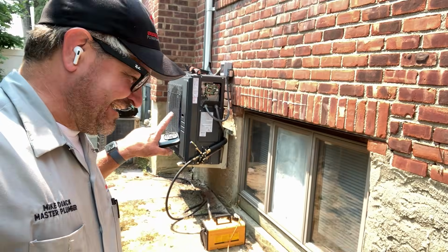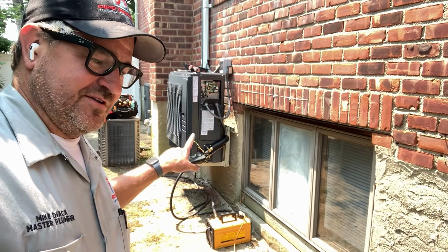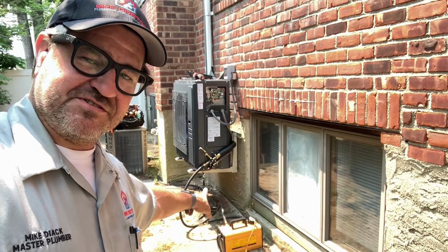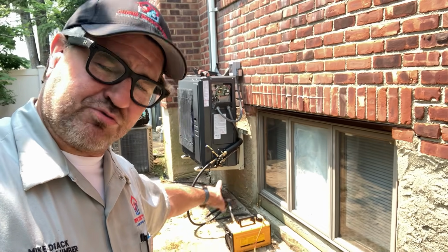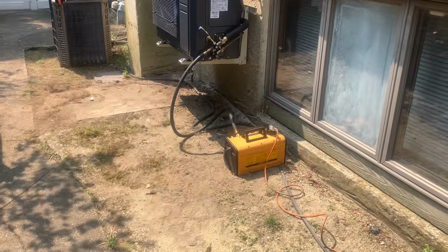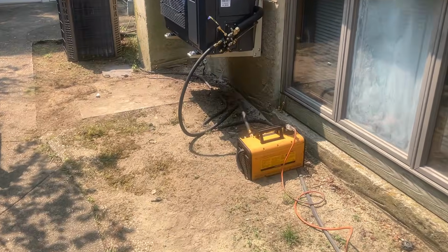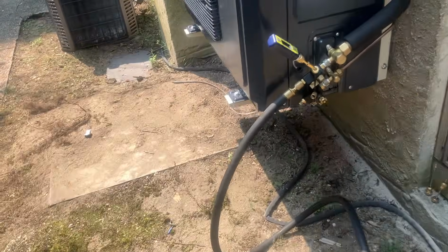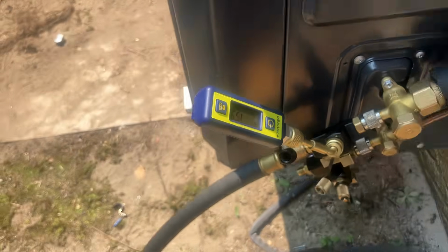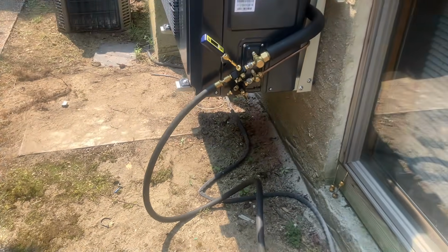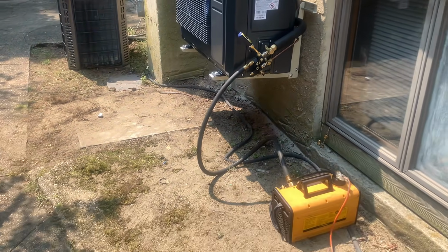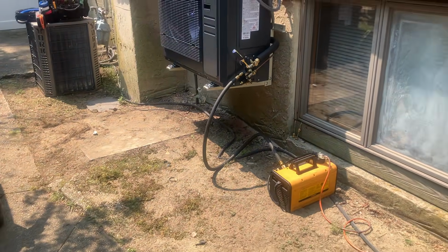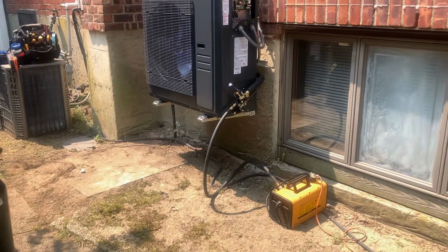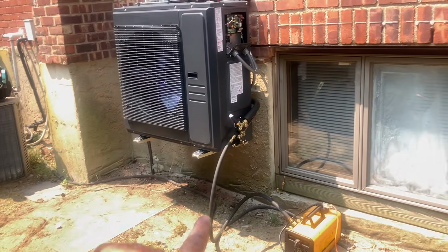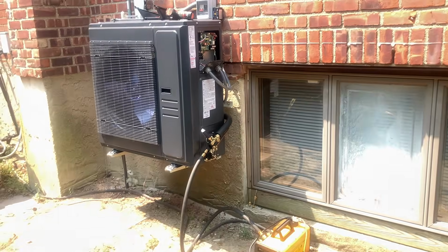But it takes a professional to hook up a micron gauge to the system while you're pulling a vacuum to prove the system is tight and dry. And that's why we use a digital micron gauge. We're not measuring PSI. We're measuring the amount of moisture, air, and non-condensable gases left inside the refrigeration circuit. And that refrigeration circuit is, right now, the line set and the evaporator coil.